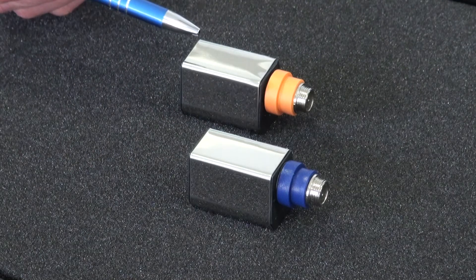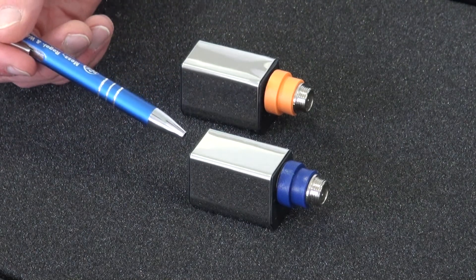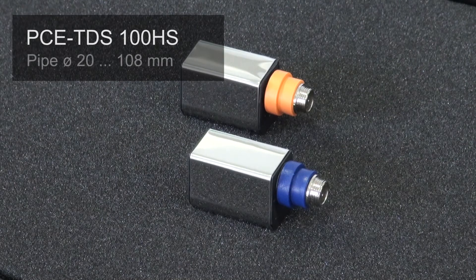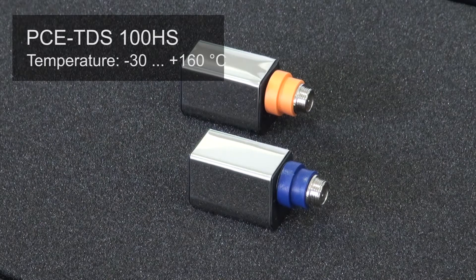The sensors of the PCE-TDS 100HS are designed for a nominal diameter from DN 15 to DN 100, corresponding to pipe diameters of 20 to 108 millimeters. The fluid can have a temperature from minus 30 to plus 160 degrees Celsius.